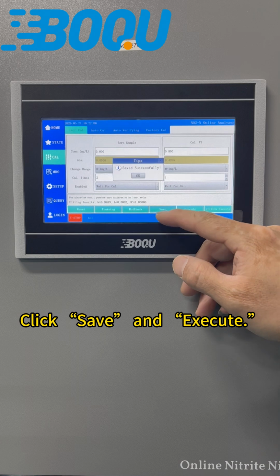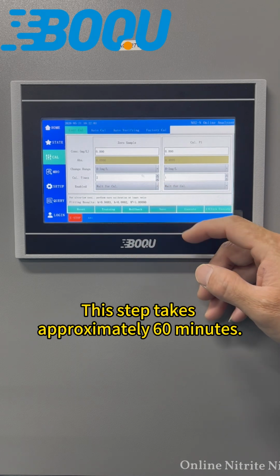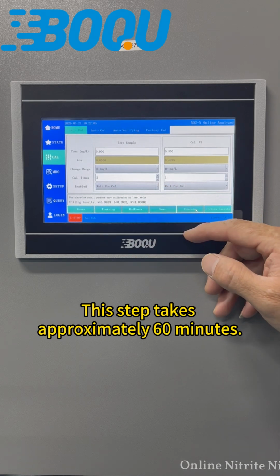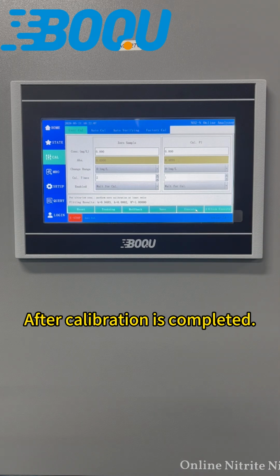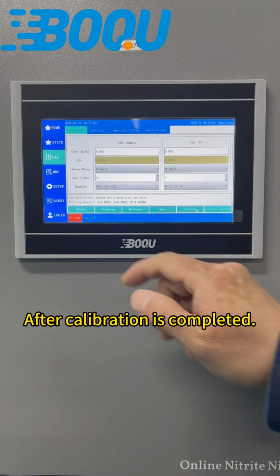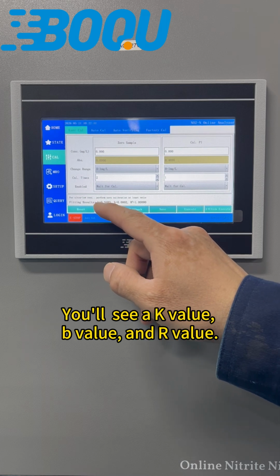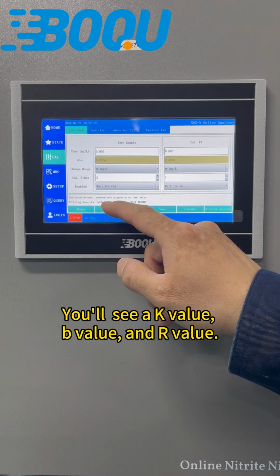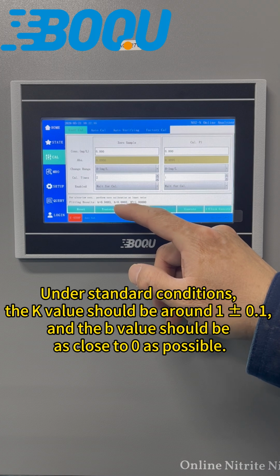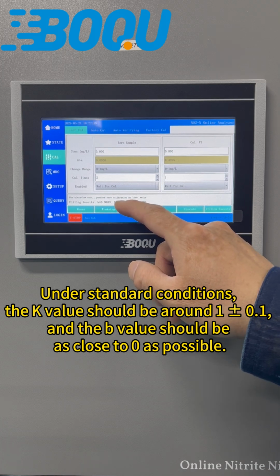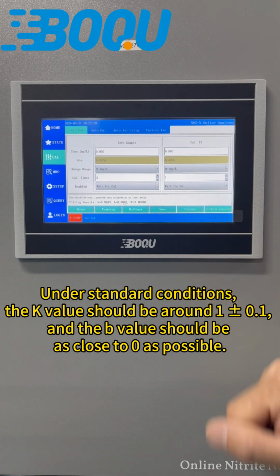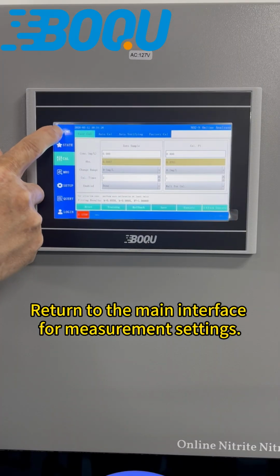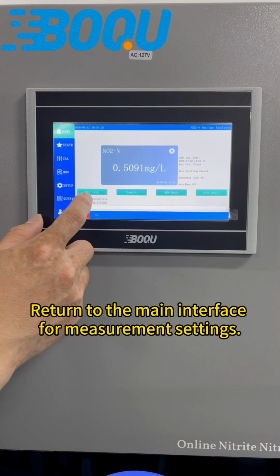Click Save and Execute. This step takes approximately 60 minutes. After calibration is completed, you'll see K value, B value, and R value. Under standard conditions, the K value should be around 1 plus or minus 0.1, and the B value should be as close to 0 as possible. Return to the main interface for measurement settings.